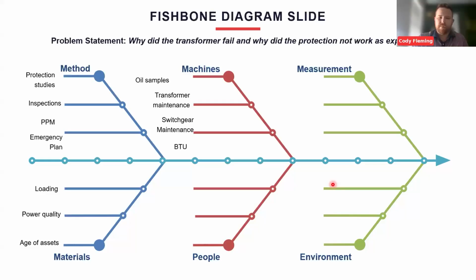And then, we touched on the transformer maintenance. You mentioned that that had been done relatively recently. You did the partial discharge testing, and I can't remember all the other tests that you mentioned, but you said it was maintained by a third-party vendor, and you signed off on it. And then the switchgear maintenance, that's absolutely where we go back into the validation of your arc flash study, or short circuit coordination study. Do the settings match? This is where we can start diving into the why of how that fault got so far up into the system. And then, your battery tripping units, how did you have control power, and was the breaker able to trip? Did it have the power it needed to do its job?